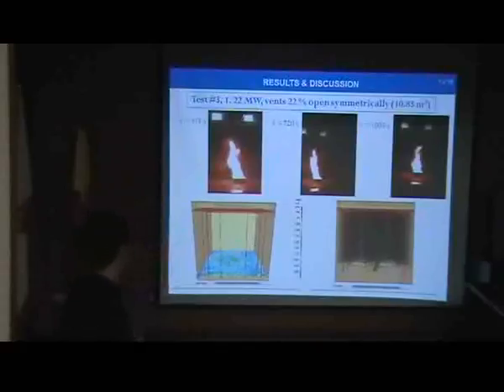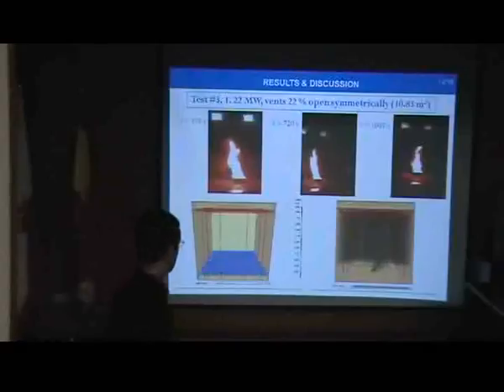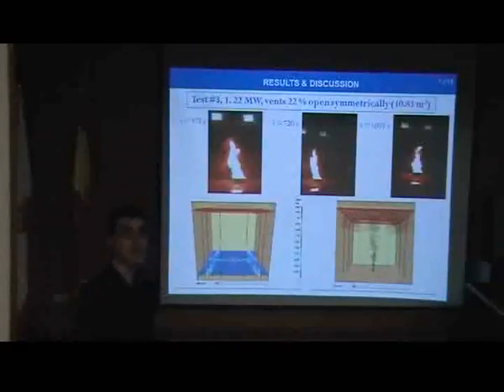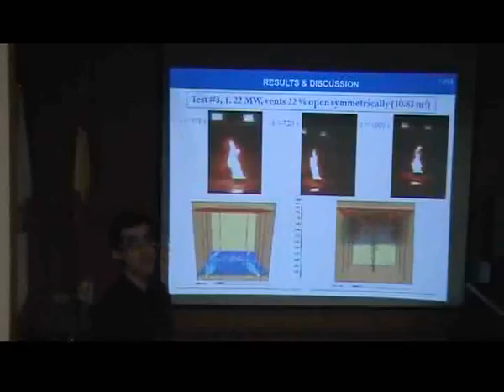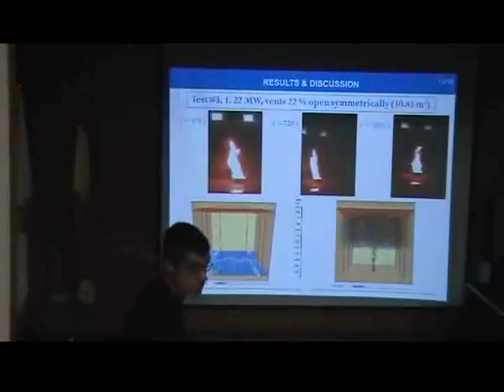This circular stream affected the flame and plume, which even lost their verticality. Also, it has been observed that the mass interchange across the smoke layer interface has been enhanced due to this perturbation, and therefore the smoke layer height has been increased.